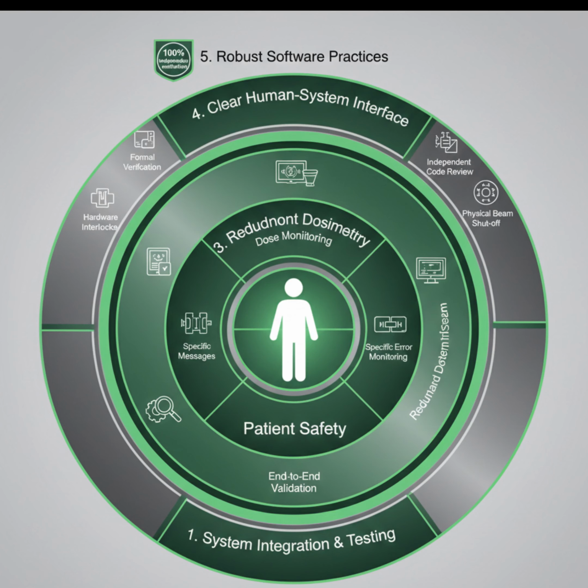The physical failure, the uncontrolled beam, was enabled by a system that had placed too much trust in unverified software and too little emphasis on defense in depth. The Therac-25 accidents fundamentally changed how engineers and regulators think about safety-critical software. The lessons extend far beyond radiation therapy machines. They apply to any system where software failures can cause physical harm.